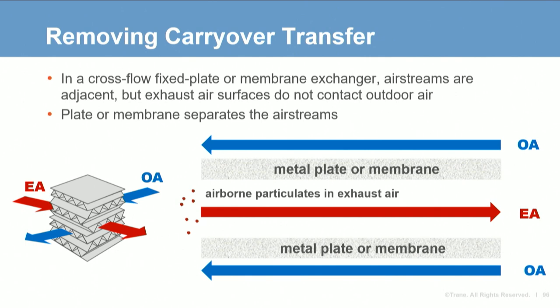To remove the first source, the static pressure in the outdoor airstream can be maintained higher than in the exhaust airstream. To remove the potential for carryover transfer, choose an exchanger that does not cycle exhaust air and outdoor air through the same channels. While wheels always have some potential for carryover, the cross-flow heat exchangers — either with metal plates or membranes — do not. The metal plates or membranes are a solid barrier between the two airstreams. Particulates and airborne viruses continue to pass through the exchanger but there is no cycling of outdoor air in the exhaust channels, removing the potential for transfer by carryover.